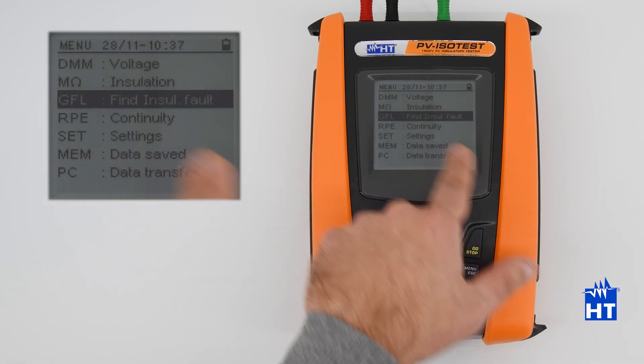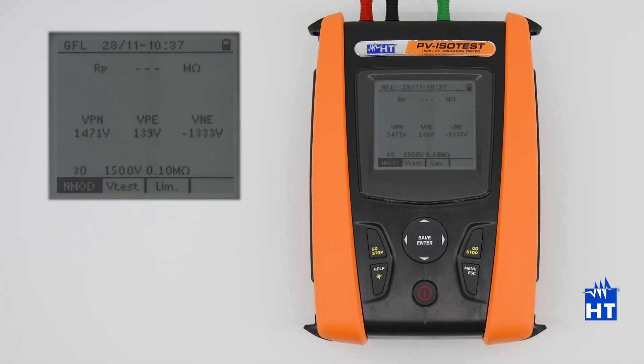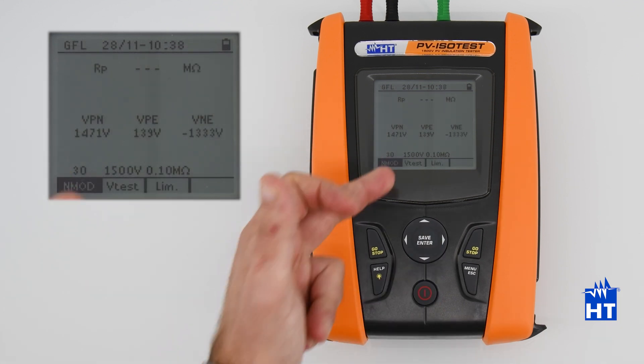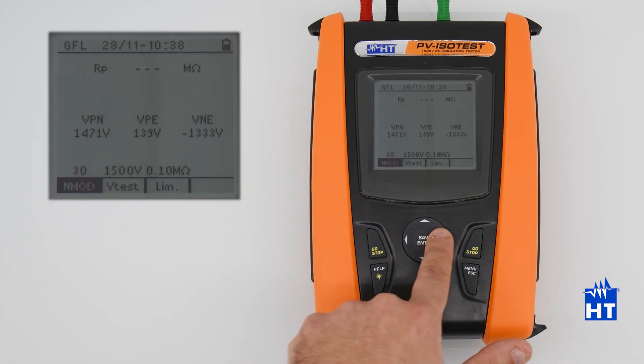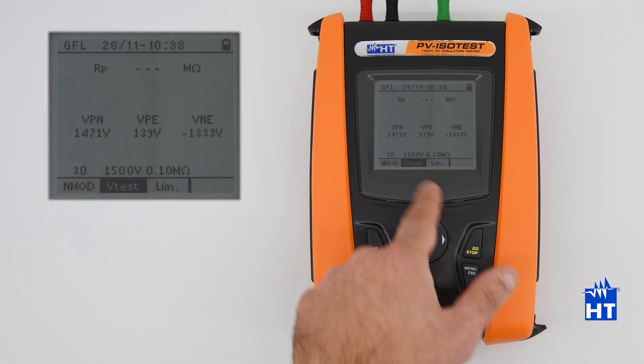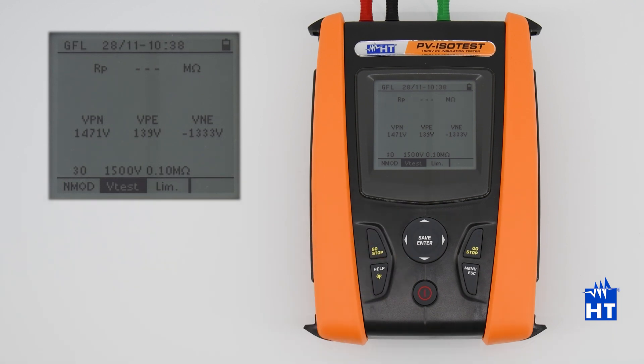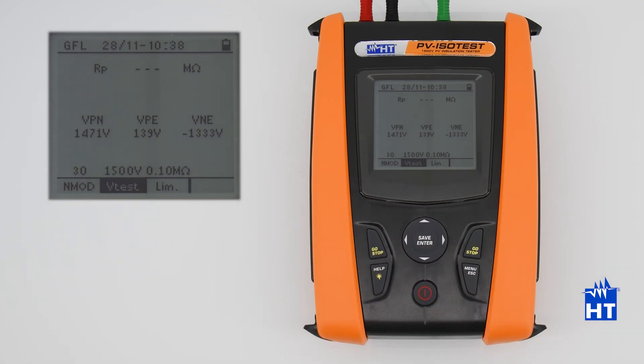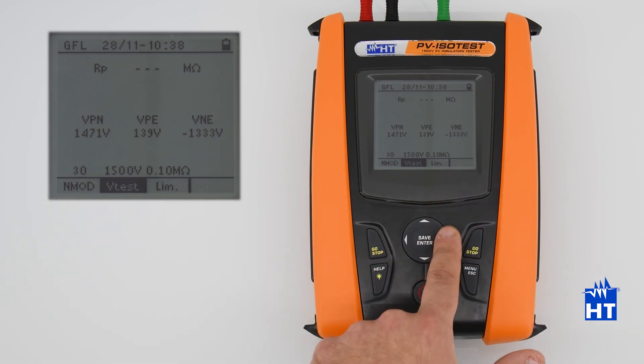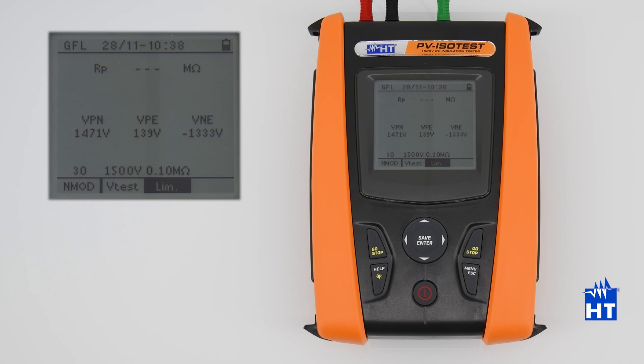Confirm, then we can select the number of modules of our string and the nominal voltage of our string — in this case 1500 volts. As you can see, we have a voltage between positive and negative of about 1470 volts. The limit set is about 0.1 megaohm, which is the lower limit for calculation of a fault.